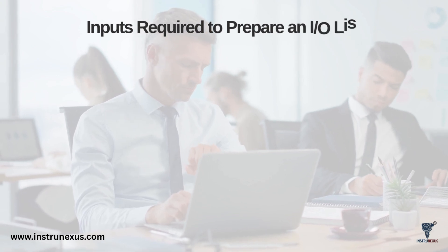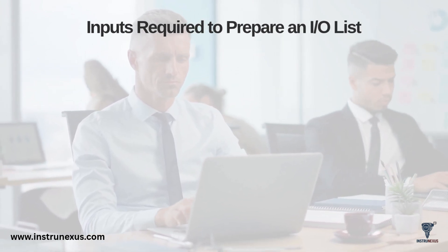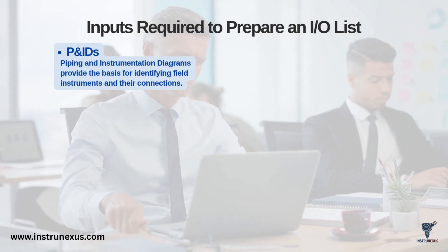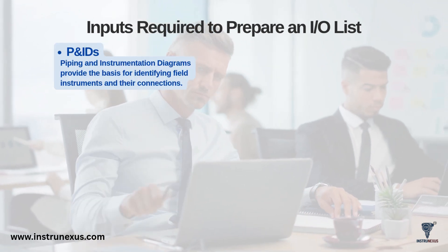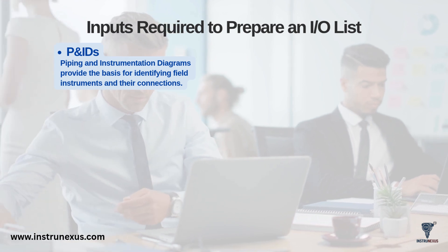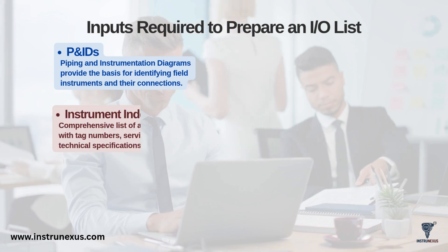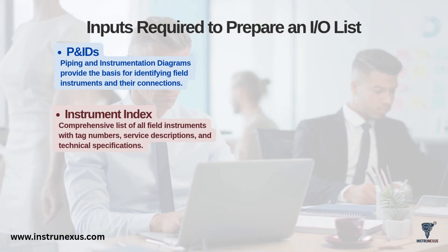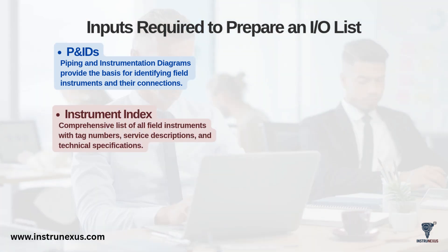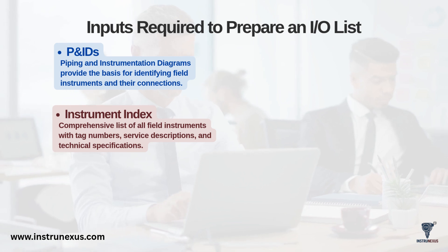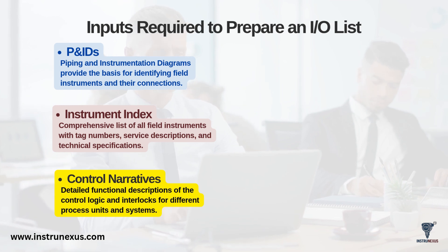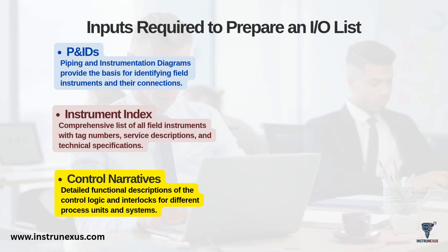A high-quality IO List is only as good as the information you put into it. There are several key input documents required. First, the P&IDs – piping and instrumentation diagrams – which are the maps that provide the basis for identifying every field instrument and its connections. Second, the Instrument Index: a comprehensive list of all instruments providing their tag numbers, service descriptions, and technical specifications. Third, control narratives, which describe how the process is supposed to be controlled, detailing the functional logic and interlocks.